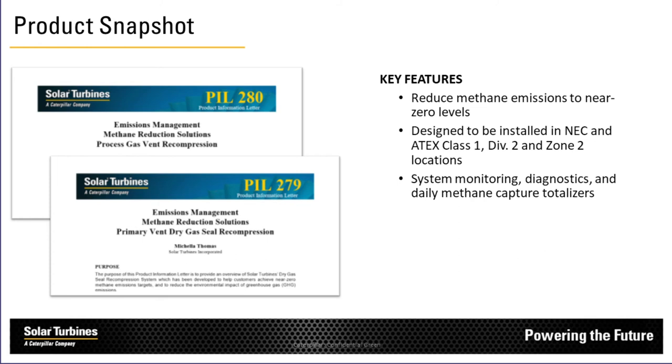We have designed the product for installation worldwide. So we have it designed for NEC or CEC Class 1 Division 2 areas or ATEX Zone 2. We use a lot of Division 1 and Zone 1 components. We can meet IECEx when requested. As I highlighted, two case studies in the US, but we do have installations in Europe and we have an ongoing installation in Canada at this time.